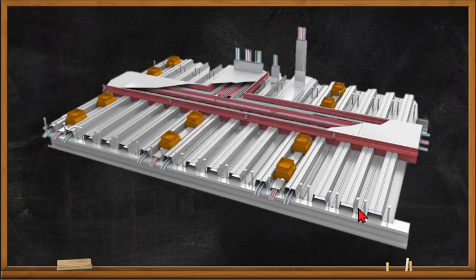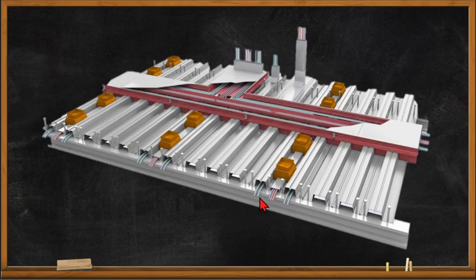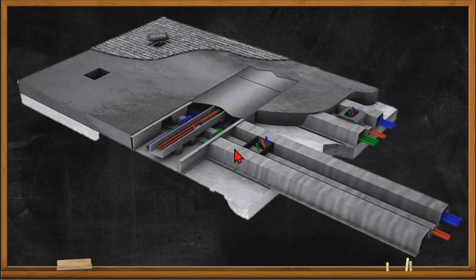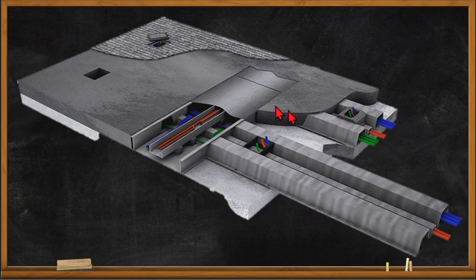The cellular metal floor raceway is defined in Article 3.74.1.2 as the hollow space of a cellular metal floor together with suitable fittings that may be approved as an enclosure for electric conductors. It has the same parts as the cellular concrete floor raceway — a header and a cell — and likewise cannot be used in corrosive environments or commercial garages. This shows an example of a cellular metal floor raceway with the metal channels and conductors, and an example of a cellular concrete floor raceway with the cells and precast concrete.